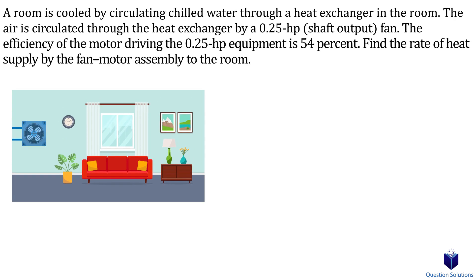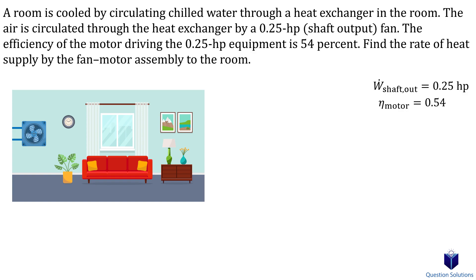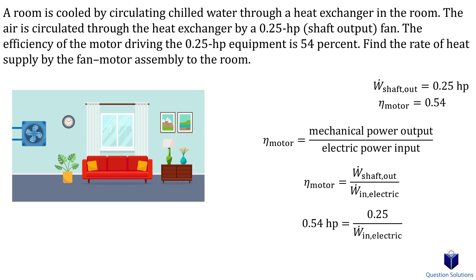Let's look at an example. We have a room cooled by circulating cold water through a heat exchanger, with air circulated by a 0.25 horsepower fan. The efficiency of this fan motor is 54%. We need to figure out how much heat is being added to the room due to the fan. All the electrical energy consumed by the motor — including the shaft power — is dissipated as heat, so we're really looking for the total electric power the motor consumes. Note that the 0.25 horsepower is shaft output.